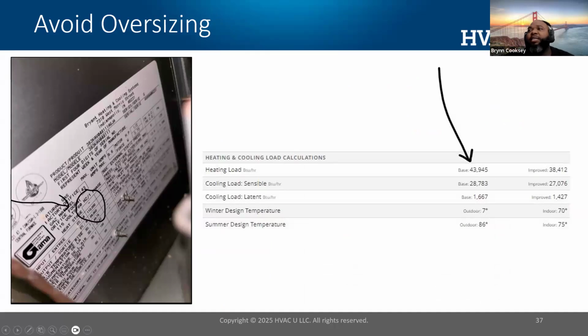Systems are often oversized. This is a load calc report that we've done with the customer. And if you see here, it's pretty small, but this customer had a furnace size that was 110,000 BTUs per hour. So if I try to replace that like for like with a heat pump, one, they don't make one that large, and two, it would be a huge mistake to do that without doing a load calc. This is a software report from an energy audit, and look at the heating load, and this is base. This is prior to me doing any kind of weatherization. All right, it's under half the capacity of the system before I do any weatherization. And after I do the weatherization, it drops down even more. So the bad habits of swapping equipment like for like, not evaluating the building shell and the building features, if you do that with a heat pump, you're going to run into some massive operational problems.